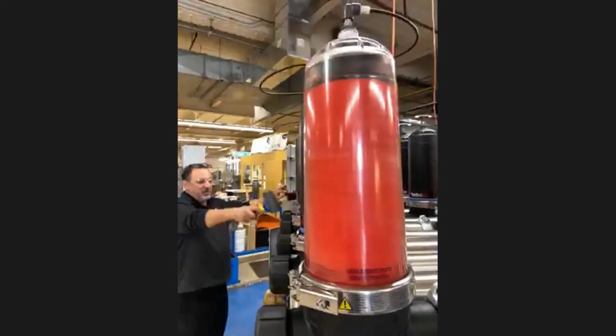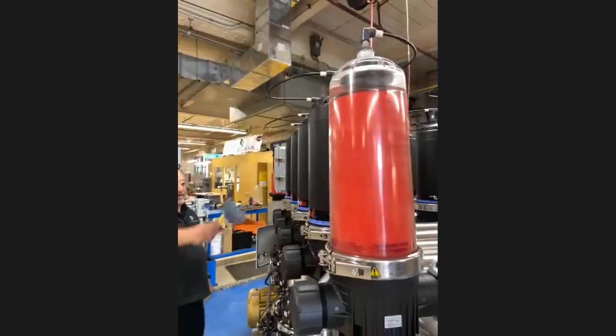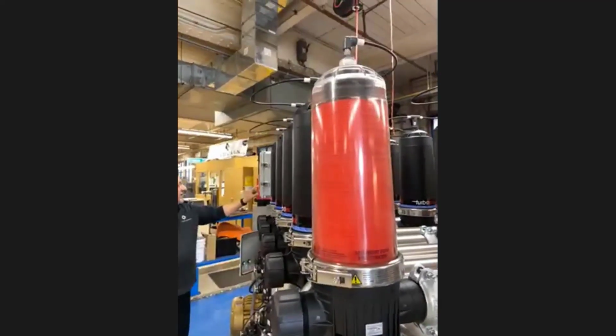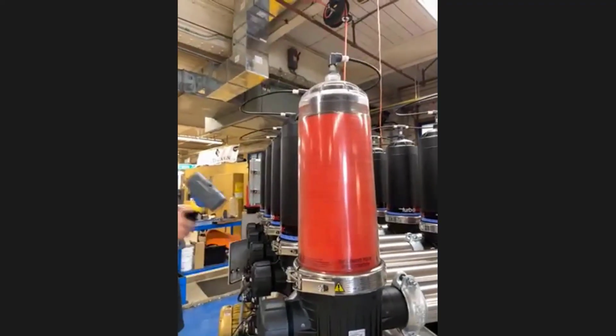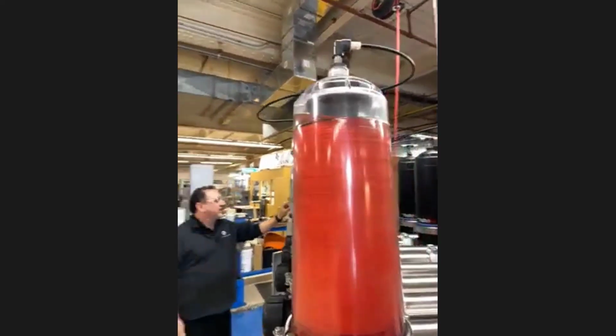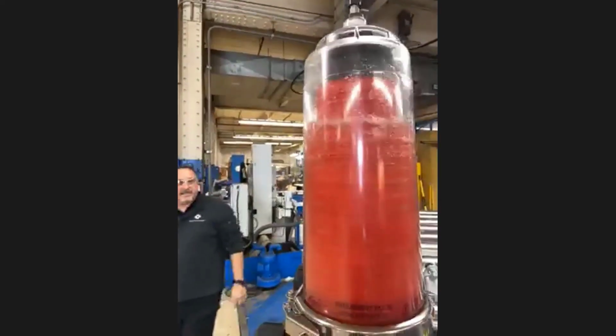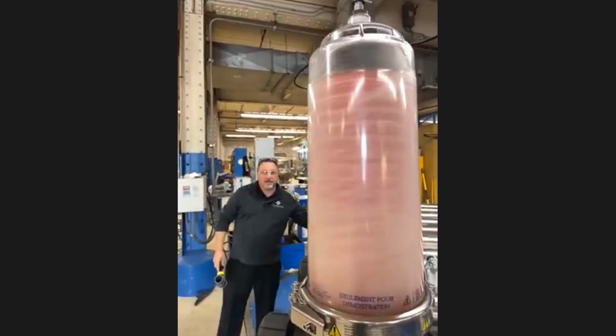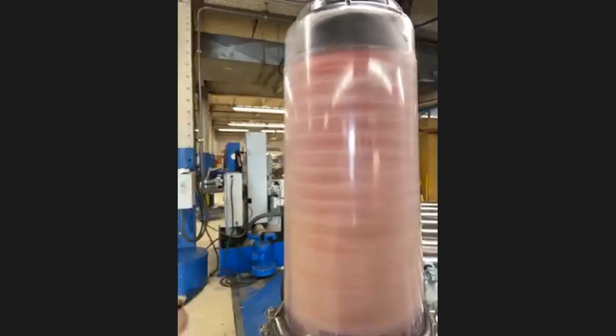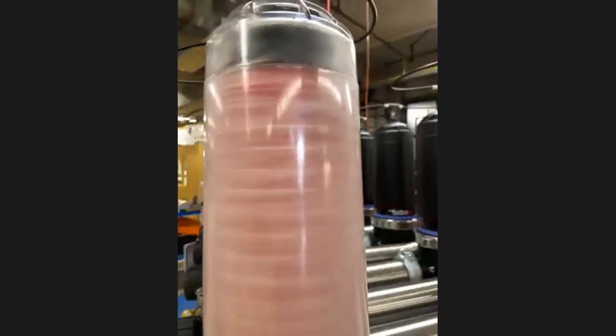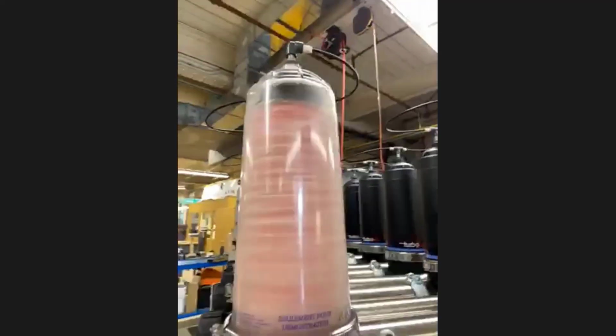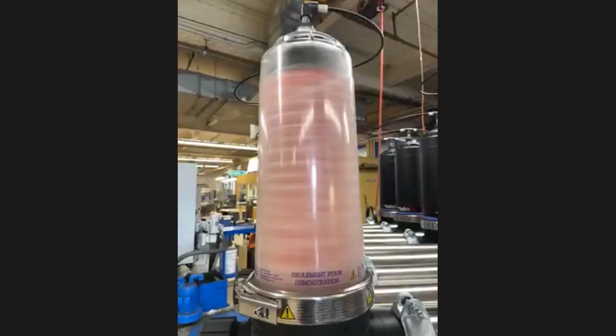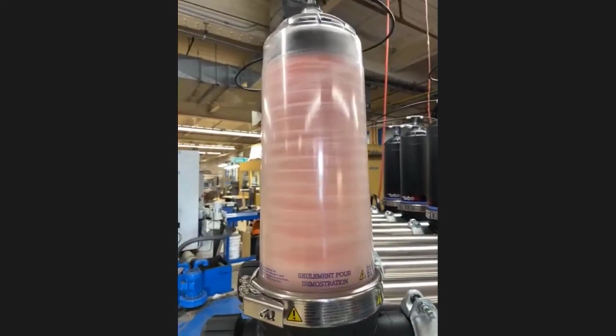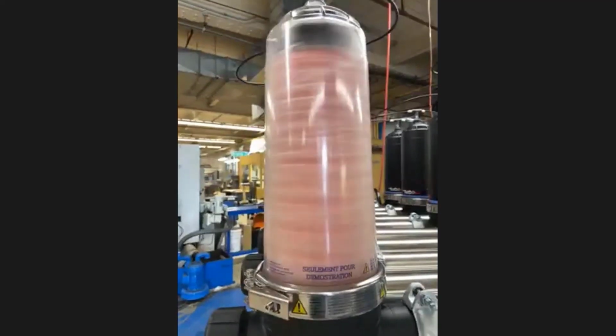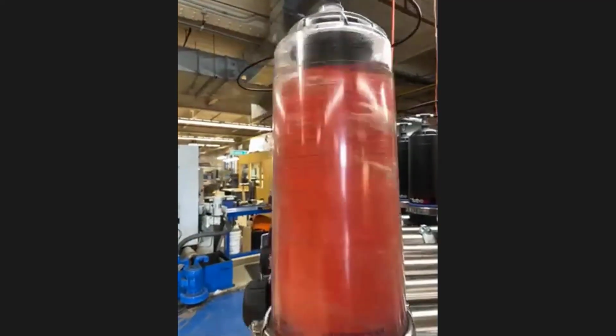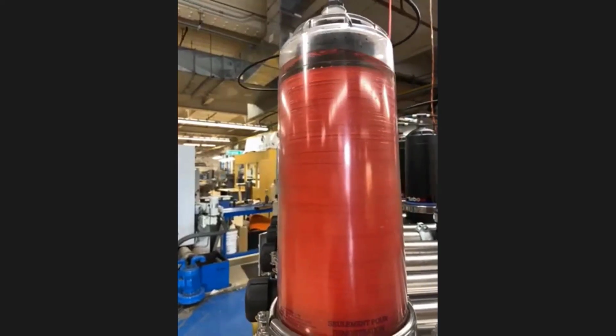Now it's going to number 2. Fast forward to number 3. Fast forward to number 4. And the next one's going to be 5. And I'm going to fast forward to that right now. So what you're going to see, there you go, is the disc separate and the 120 jet spray out tangentially, scouring and cleaning the disc. I left it on for a little extra time. It only takes around 10 to 15 seconds to clean the disc. I just left it on a little extra so you can see what it looks like. And now we're back into filtration mode.